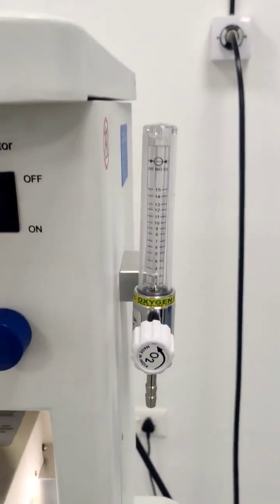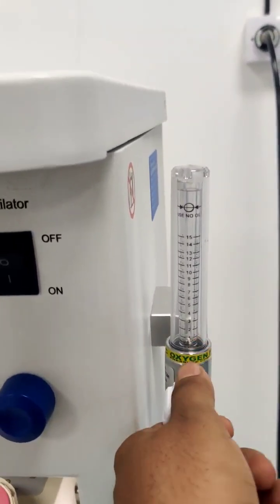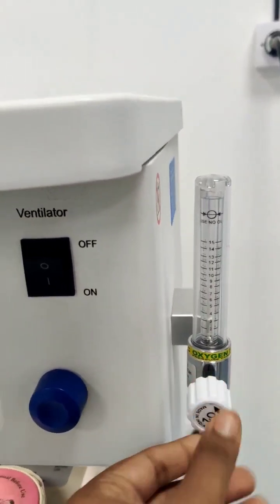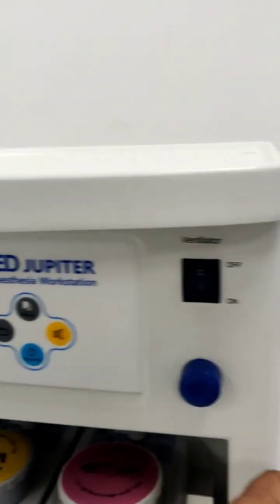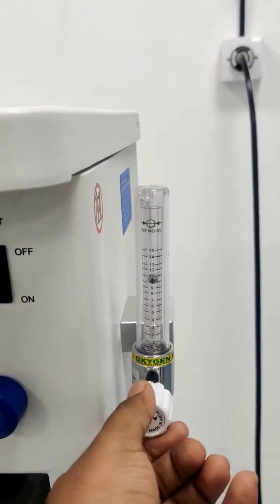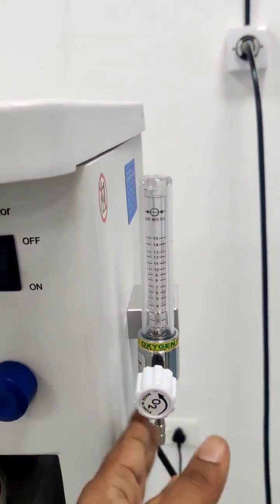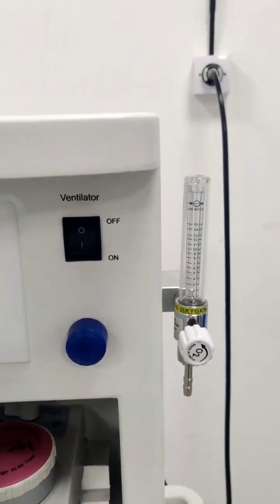This is the auxiliary flow meter which we are giving. This will operate even when the machine is turned off. If I turn this machine off, you can still use it with the help of the knob over here. You can connect the venti mask and you can always give supplemental oxygen to the patient.